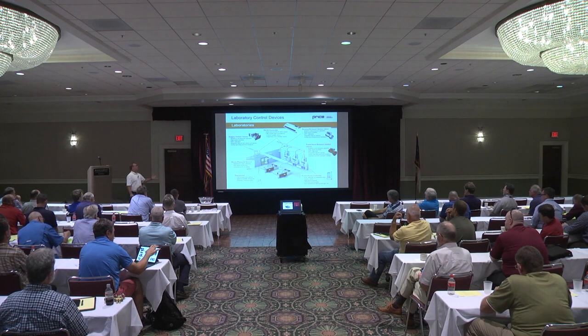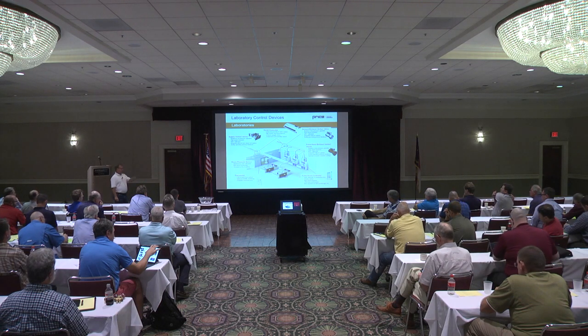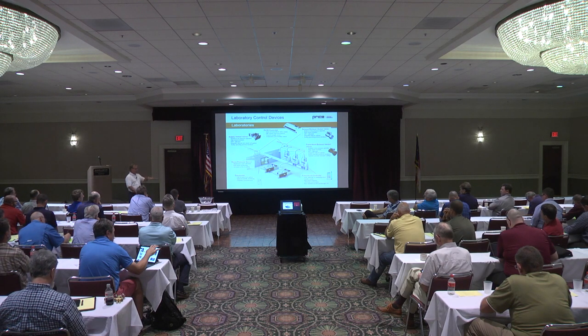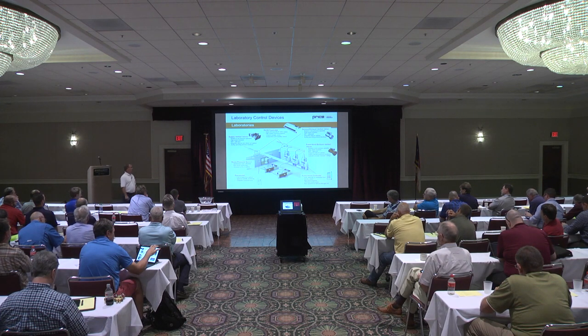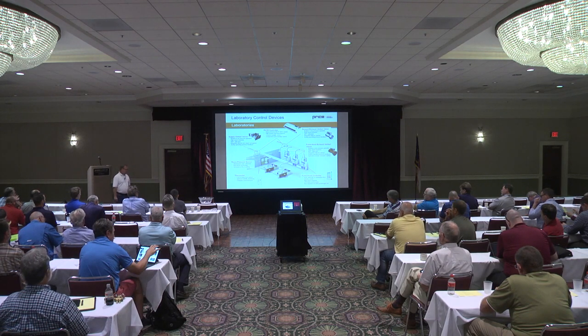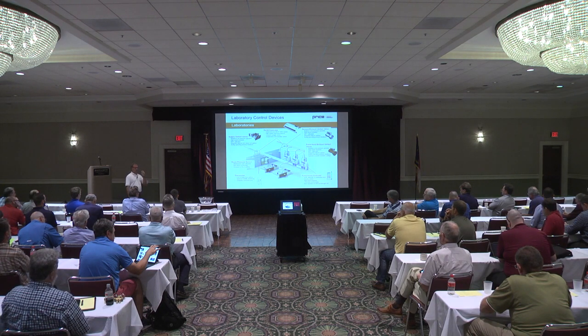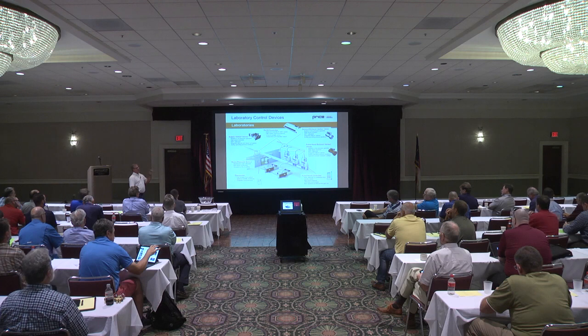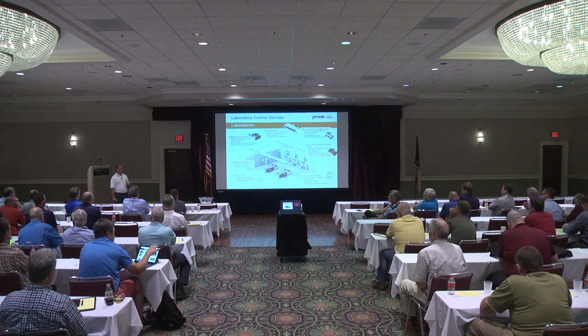Say you had a space with 10 fume hoods, and you walked in to start the day, the room was under control, 72 degrees. Everything's wonderful. Hot water coils, 25% open. And they opened every one of those fume hoods at the same time, and they went from 3,000 CFM to 12,000 CFM. It's going to happen immediately because those fume hoods are going to need the airflow for safety, and the room's going to need the airflow for pressurization control. So the supply will dump that volume of air into the space.